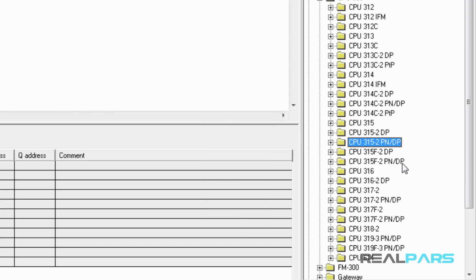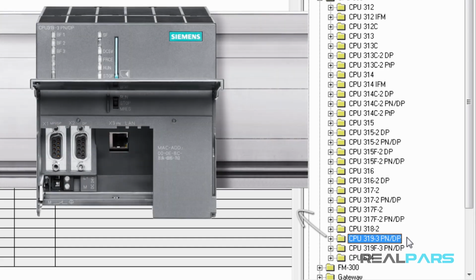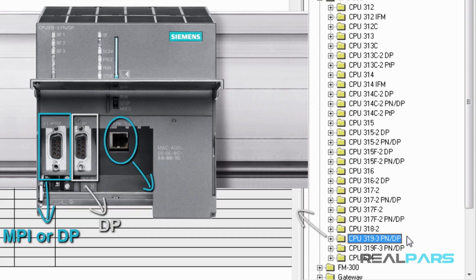Another type of CPU we have here is the CPU 319-3 PNDP. The 3PNDP in the CPU code tells us that the CPU has three ports on it. The first port could be used as either an MPI port or a DP port. The second port could only be used as a DP port, and the third port could be used as a Profinet port in an industrial Ethernet network.